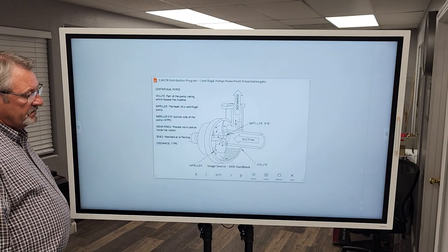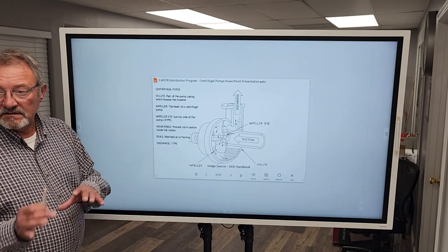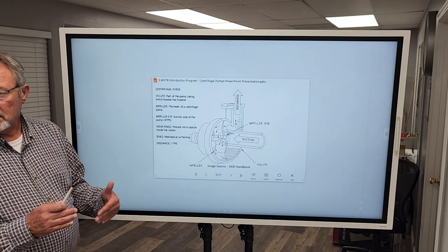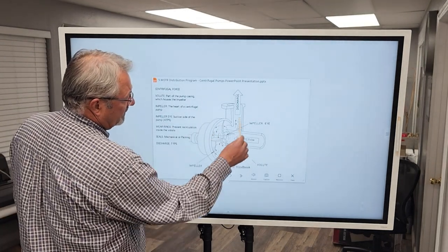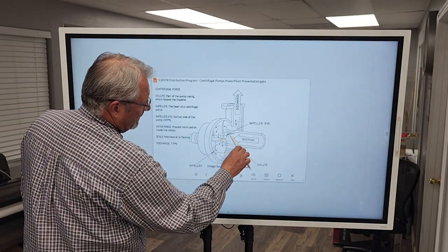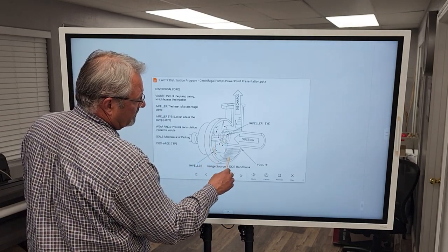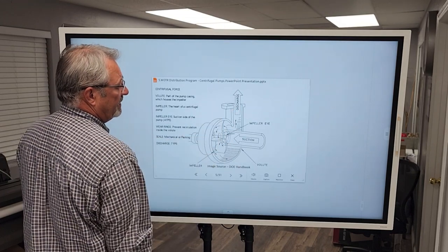Every pump has a suction side and a discharge side. The suction side is where the water enters the pump; the discharge side is where it's leaving. Here we have a cutaway, and you see what I was talking about with that snail look to it. As the water comes in, it enters through the impeller eye. The impeller spins the water around, building up centrifugal force to discharge it at a 90-degree angle — kind of like a baseball pitching machine that rotates, grabs the ball, and pitches it.